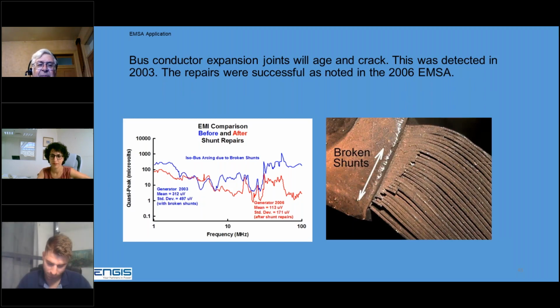Every bus has expansion joints. You have temperature cycling, you have weather conditions, so they expand and contract. Very popular are leaf type expansion joints. They work harden and break. This particular one is about 30 years old.